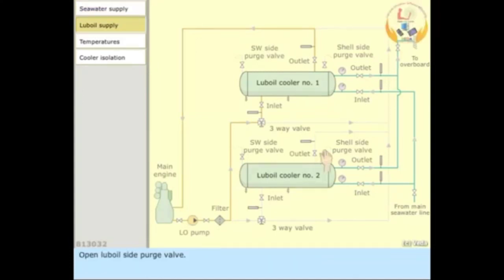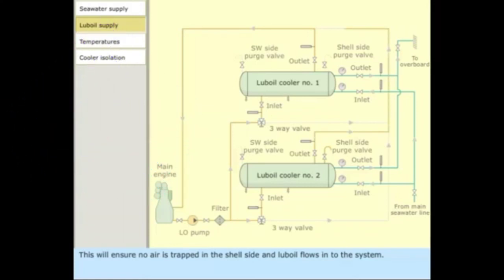Open lube oil side purge valve. Open the lube oil inlet valve by one turn. When the lube oil comes out of the purge valve, open the lube oil outlet valve gradually to full open position. This will ensure no air is trapped in the shell side and lube oil flows into the system. Close the purge valve. Open the inlet valve fully.